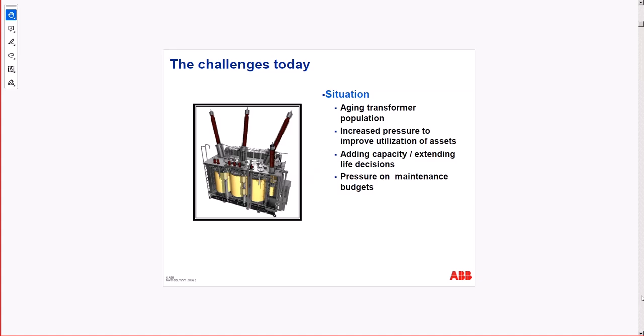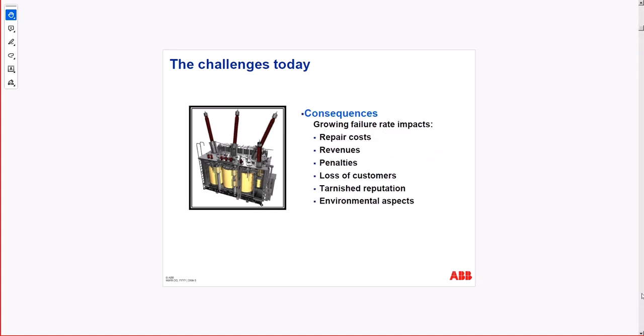Challenges: aging population, increasing pressure to improve utilization of the assets longer than originally we accounted for. Let's say we had 30 years in plan, but now we passed 50 years and we still consider the same power transformer as still having some life in it, especially if we do the reconditioning, changing the most important parts that deteriorate, like bushings and gaskets, and changing the oil and so on. So we will see what kind of tests are recommended to acknowledge the situation of the transformer and what can be done to fix it.